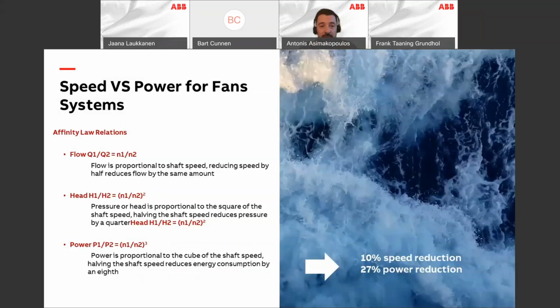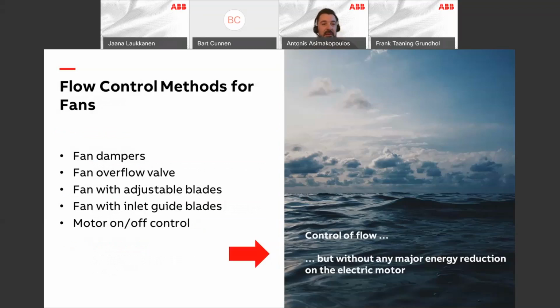Regarding speed and power for fan systems, the affinity laws apply for flow, head and power. All in all, we can see that with a very small speed reduction in a fan or a pump of around 10%, we can achieve a 25% reduction in the power of this fan, which is quite important. The current flow control methods for fans consist of fan dampers, fan overflow valves, fans with adjustable blades, with inlet guide blades, in some cases only motor on-off control. Of course, in all of these cases you control the flow, but unfortunately you don't have any major energy reduction on the electric motor.